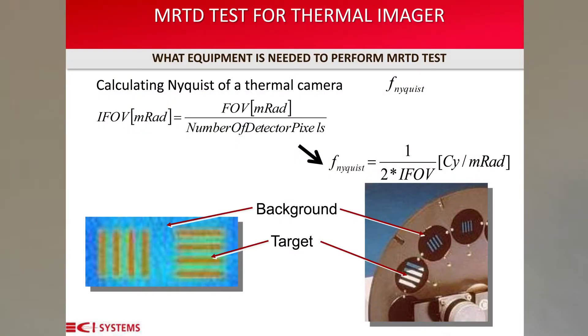The Nyquist limit of the camera is often received from the optical designer or camera manufacturer, but it can also be estimated by the following equation. Remember that the actual performance of a camera or system is based on many variables, from the window protecting the camera, lens, detector, through the image optimization algorithm, and the size and quality of the viewing monitor used by the operator.